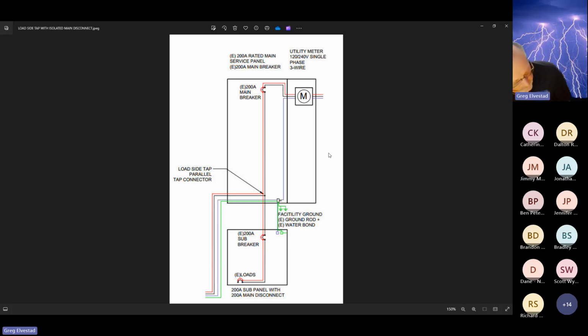This drawing represents a meter main. No bus bar outside. You just got a circuit breaker and a conductor going inside. There, you don't have a rating of a 120% rule, 705.12(B)(3)(2), excuse me. The 120% rule doesn't exist because there's no bus bar out here. It's very important to understand that the 120% rule of backfeed breakers only applies to the panel that can distribute load more than just the feeder going to another subpanel. So load side tap is a good way to connect. Rule out there says you have to be concerned about the conductor capacity from this point here down to the subpanel.